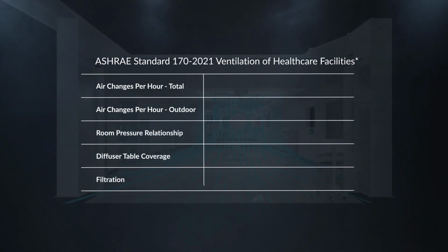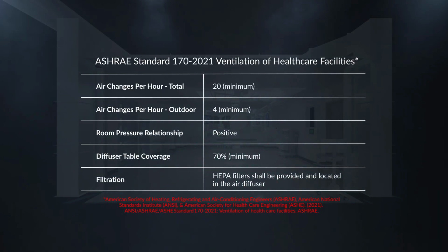Ultrasuite Climate optimizes indoor environmental quality by increasing the air change rate in the operating room by up to 3 times the ASHRAE Standard 170 minimum of 20 air changes per hour while meeting all other air distribution requirements.